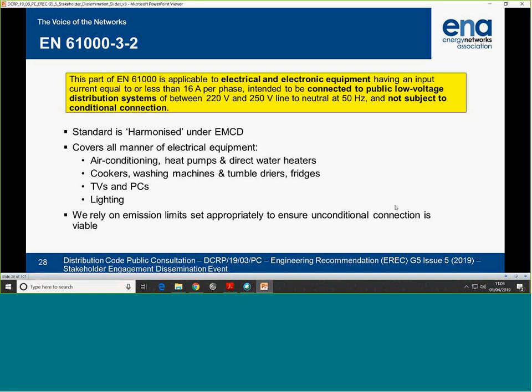When you look at this, on the right side we have the EMC directive, which is a European thing, and the document is published in the Official Journal of the European Union. So therefore, it's a harmonized standard and allows it to be called up by manufacturers. If they comply with that standard, then they meet the essential requirements of the EMC directive, and they can then sell it into Europe. We don't see that situation changing, but obviously, we know Brexit. We've sort of ignored that.